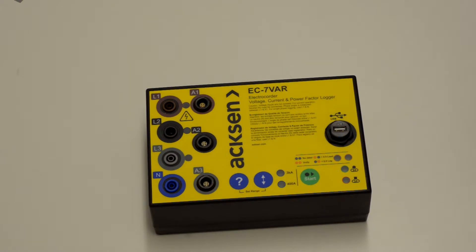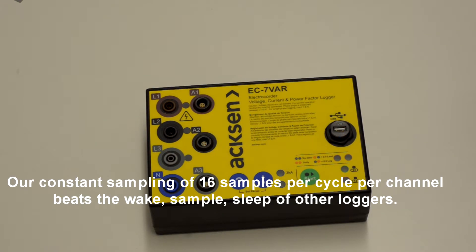It's designed to be an entry-level logger that's easy to use. It uses what we call constant sampling, which means once started, it continually samples each channel 16 times per cycle. At the end of the averaging period, which you set, it saves that data out.